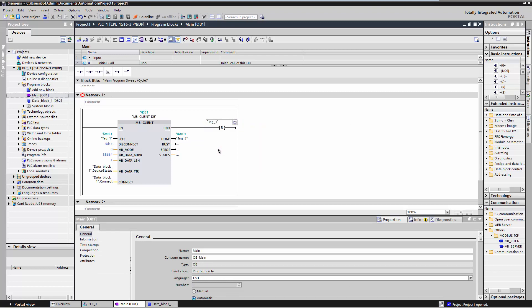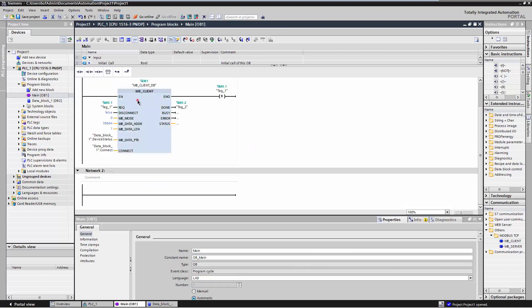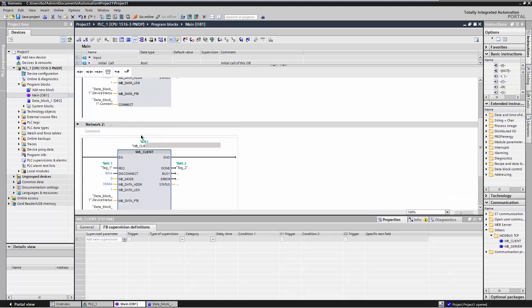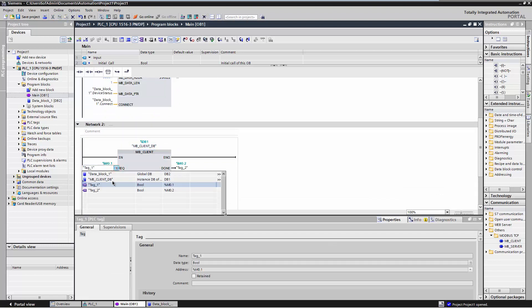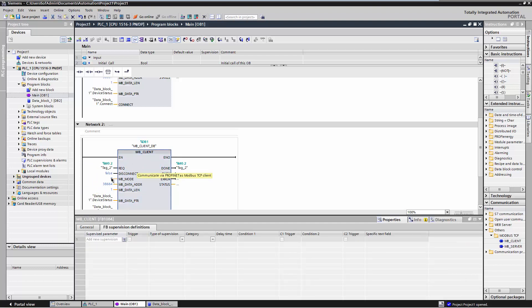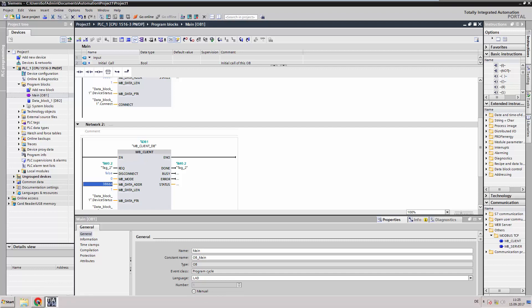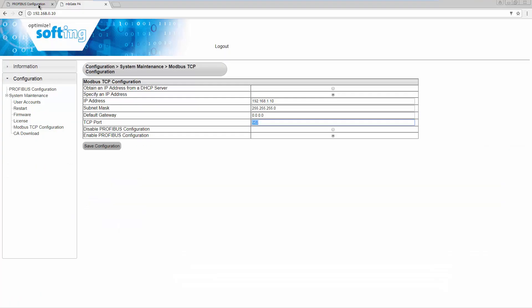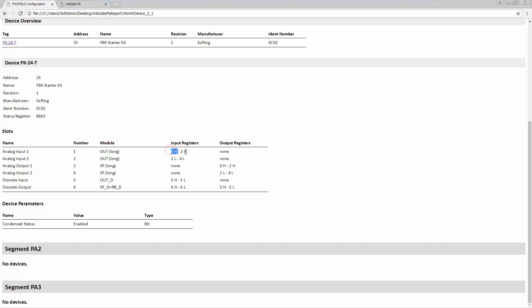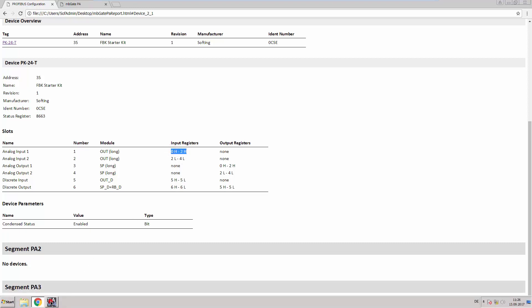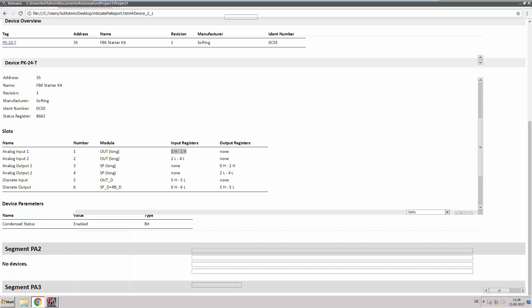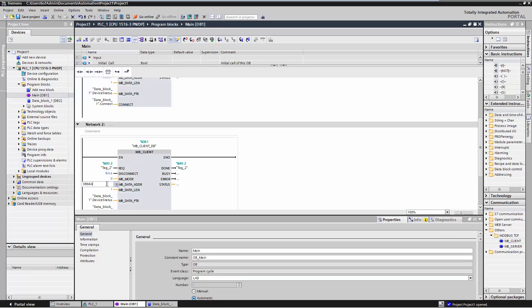To read the input data of an AI module, the created instruction is copied and must be adapted accordingly. For the input parameter REQ, define a variable that was used for the output parameter Done of the other MB Client instruction. Thus, the instruction for reading the input data is executed after the reading of the status information. For the register address, look at the Modbus mapping of the input data of the first AI module in the HTML report. It can be seen that the data starts on register 0 and occupies the first two registers as well as the high byte of the third register. Since this is input data, for register 0 you must enter 30001 in the TIA Portal.